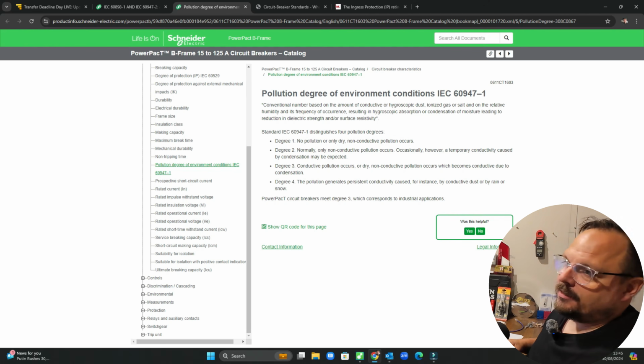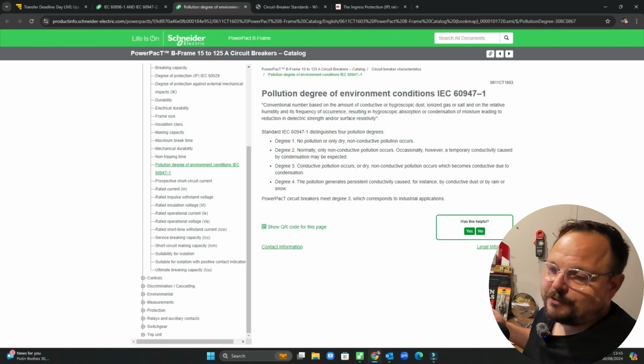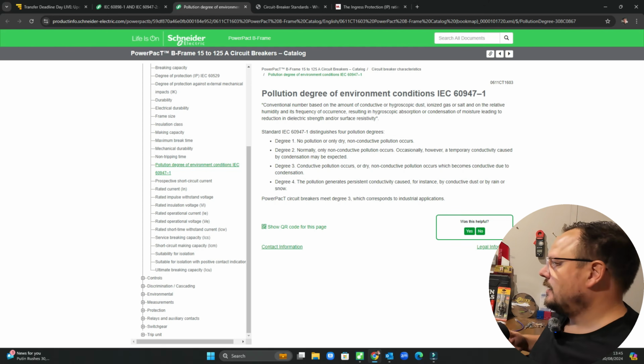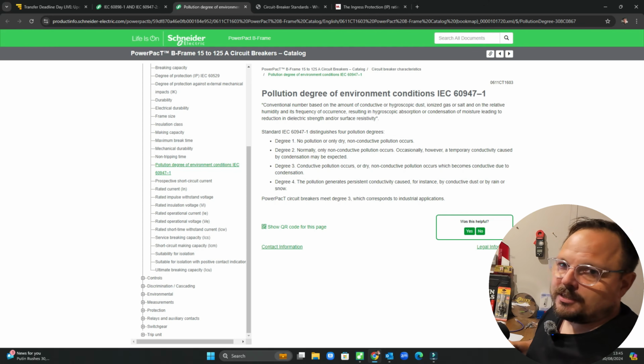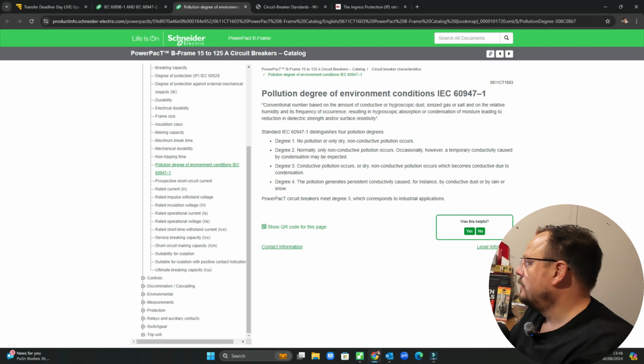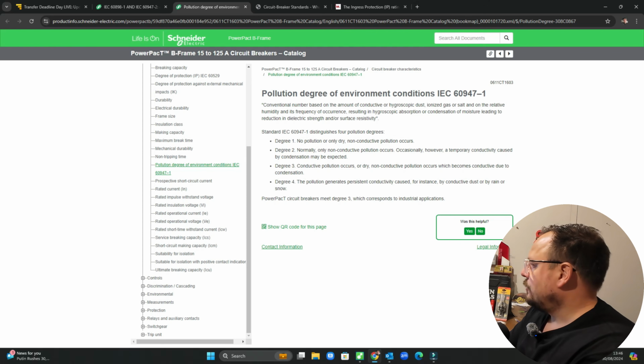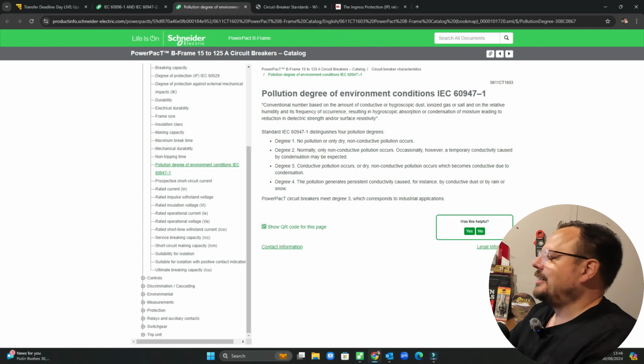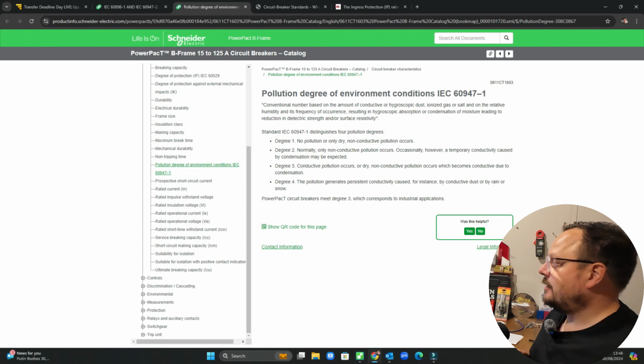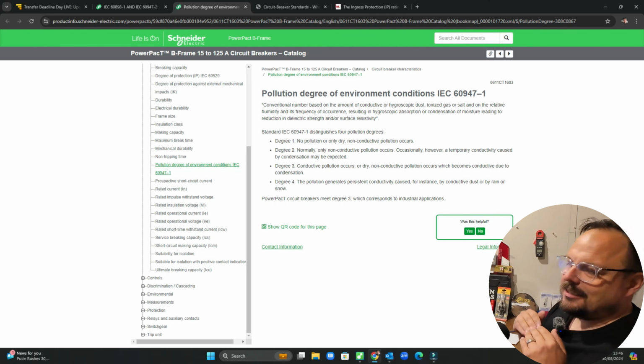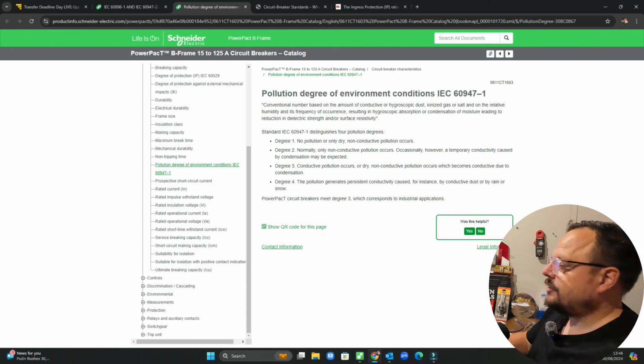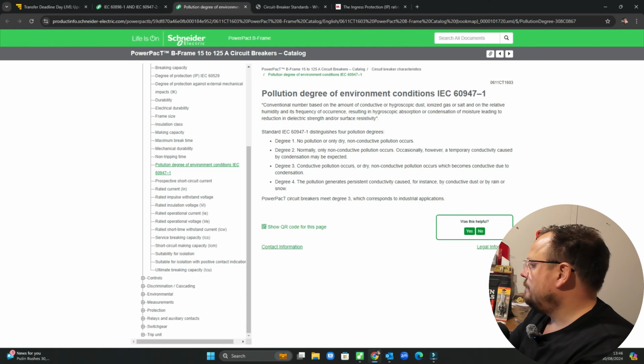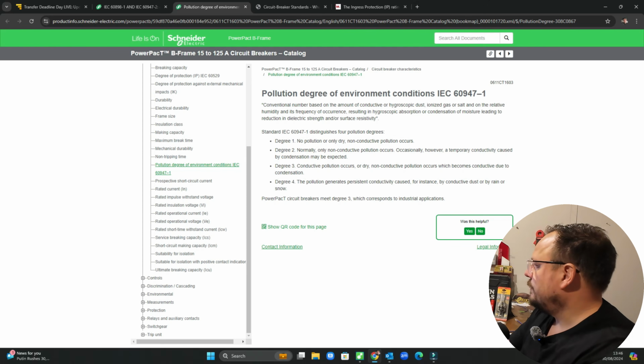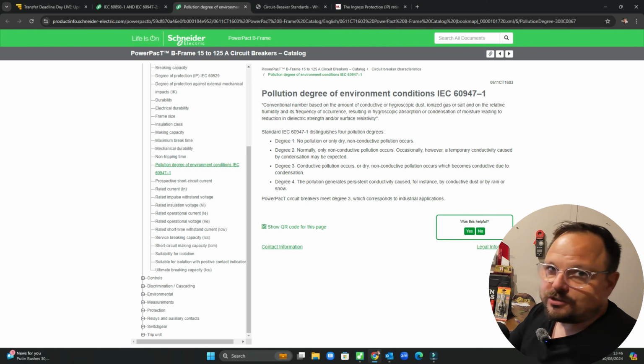There might be times where, you know, it's a humid day, the house has had a few people having showers or whatever, and the air's quite humid, and some of that can end up working its way into the enclosures and switchgear for a very short duration. It's probably a bad example, but that's kind of what that means. Degree 3 is conductive pollution occurs, or dry non-conductive pollution occurs, which becomes conductive due to condensation. So that's more like your unheated spaces, I would say, rather than directly outside. This is where there's a slightly grey area for me as to what directly outdoors actually is. And degree 4 is the pollution generates persistent conductivity caused, for instance, by conductive dust or by rain or snow.